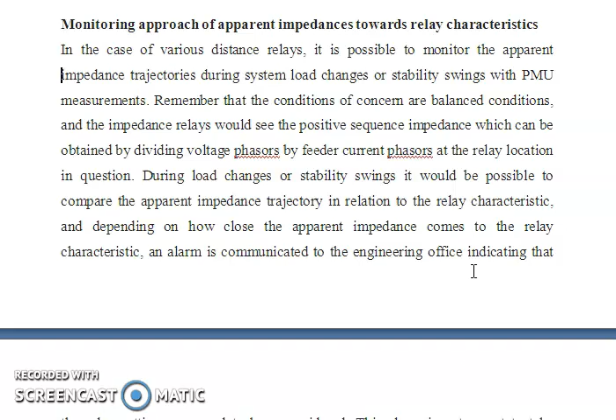Now during load changes or stability swings, it would be possible to compare the apparent trajectory in relation to the relay characteristics, and depending on how close the apparent impedance comes to the relay characteristic, an alarm is communicated to the engineering office indicating that the relay setting may need to be reconsidered. So this alarm is not meant to take action in real time, but to send a message to the engineering office that the relay settings may need to be revised or changed. This function would identify the critical protection functions which may be in danger of causing a cascading failure due to unexpected operation of the relay.